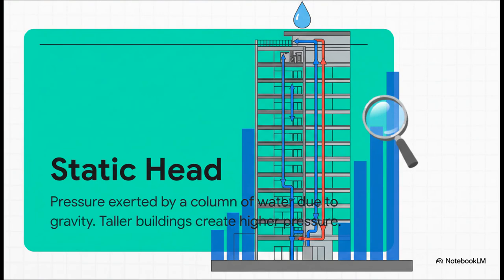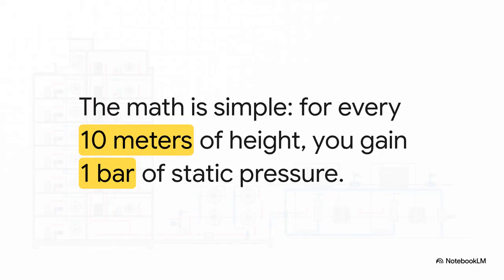So let me introduce you to the main villain of our story, static head. It's really just a fancy term for the weight of the water sitting in the pipes, pushing down thanks to gravity. And the taller that column of water gets, the more intense that pressure becomes at the very bottom. Now, what's really cool is how simple the math is to figure this out. It's a great rule of thumb. For every 10 meters you go up, you gain about 1 bar of static pressure. It's a beautifully simple formula, but man, it has some seriously powerful consequences.